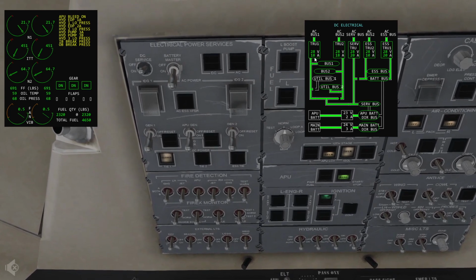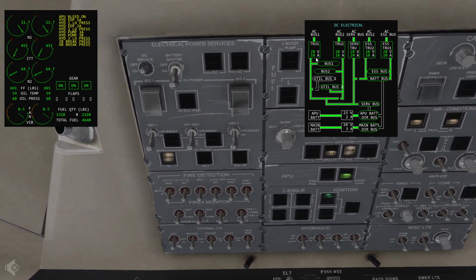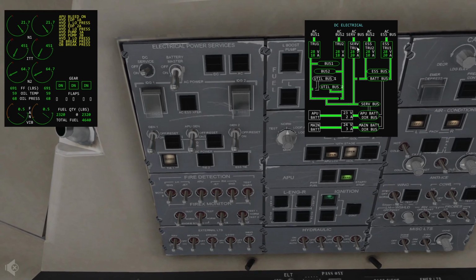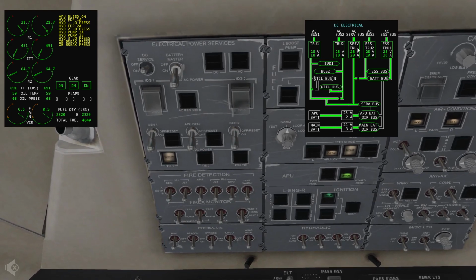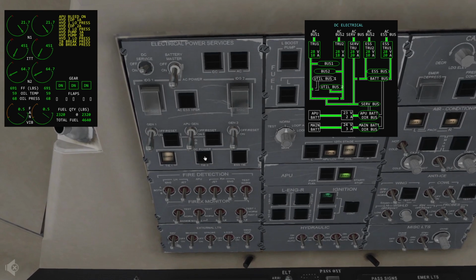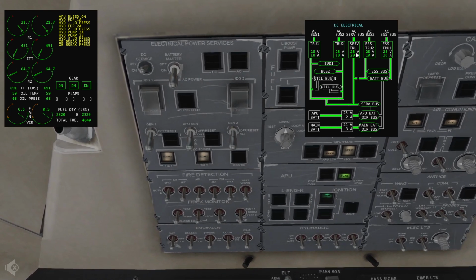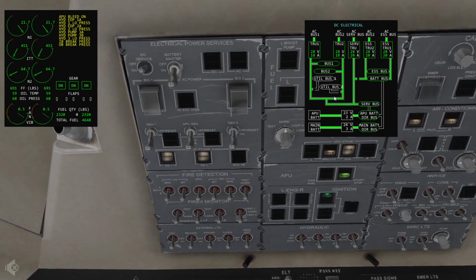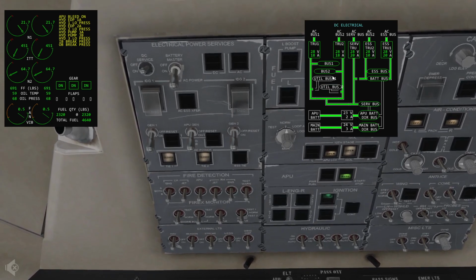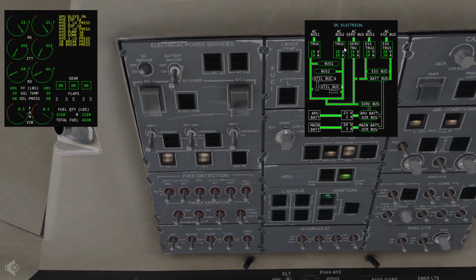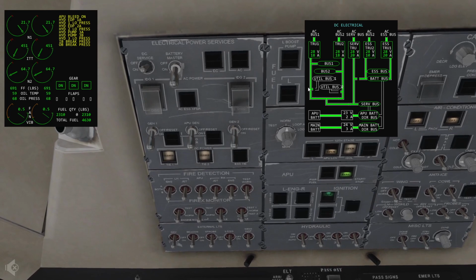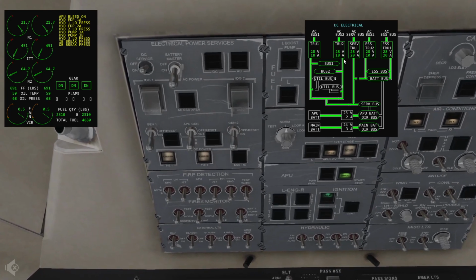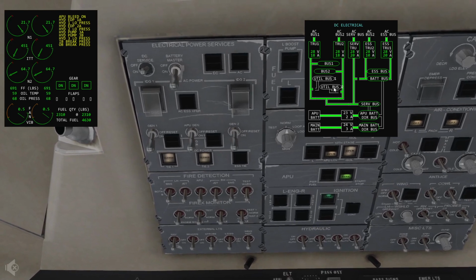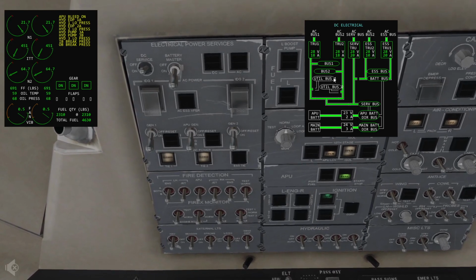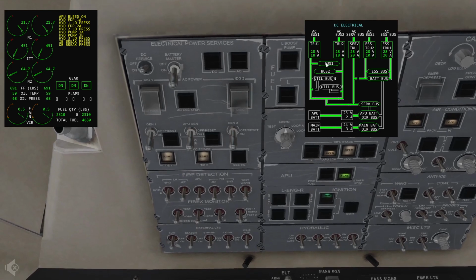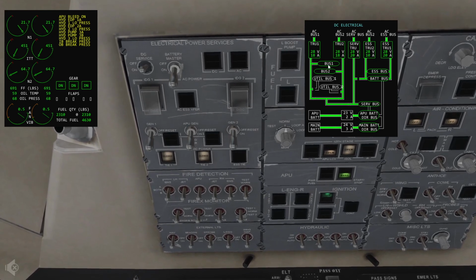If the service TRU were not available, so if there's no service TRU, both DC tie 1 and 2 would be closed. So if there's no service TRU, both these will be closed, allowing TRU 2 to power the bus 1. So TRU 2 will power the bus 1 at this point. It will provide bus 2 too, but it will load shed utility bus 2, and utility bus 1 will be load shed. So it's just to reach the DC bus 1.